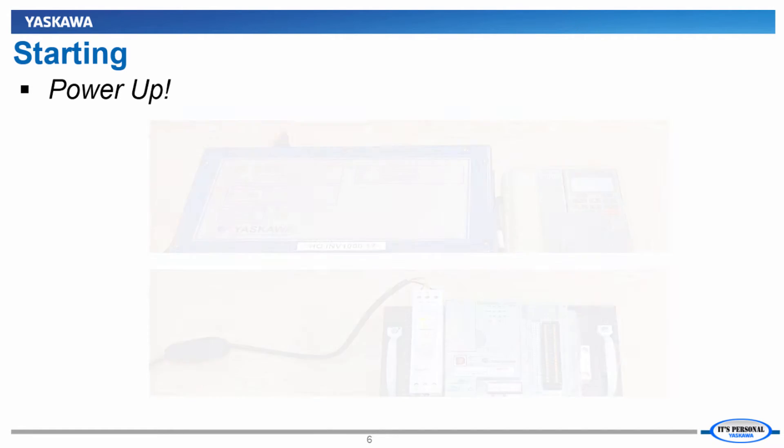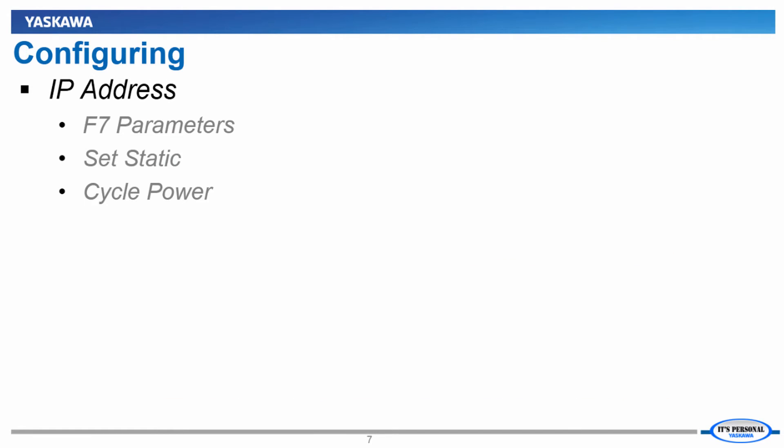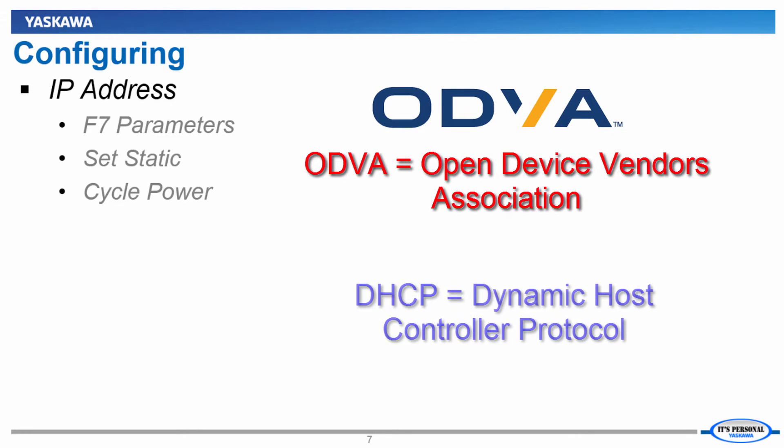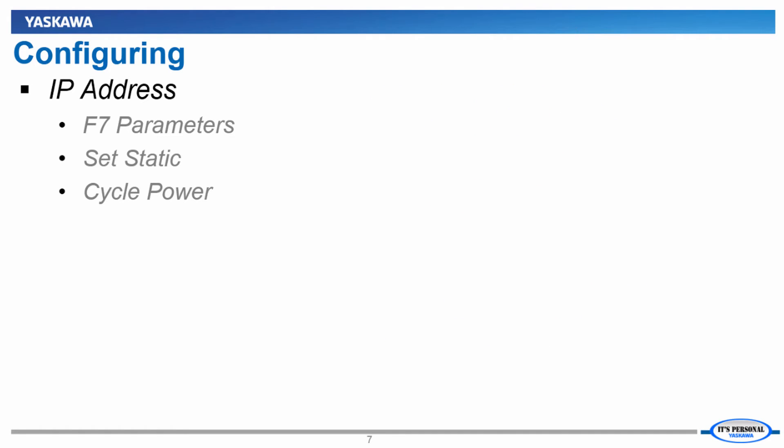Now that the devices are powered up, the first thing you'll need to do with the VFD is to program its network settings. Per ODVA, the default mode of the drive is to use DHCP to get its network settings. If you're not using DHCP, then you'll need to program the settings by hand.